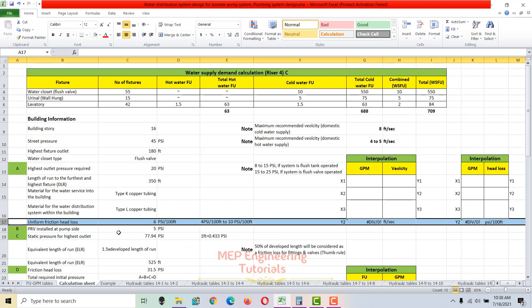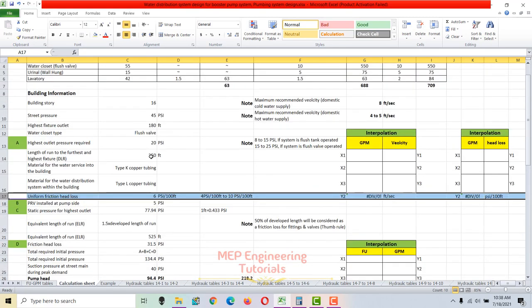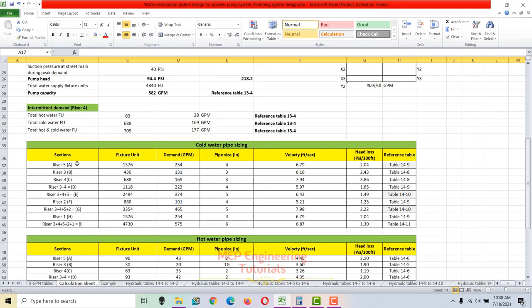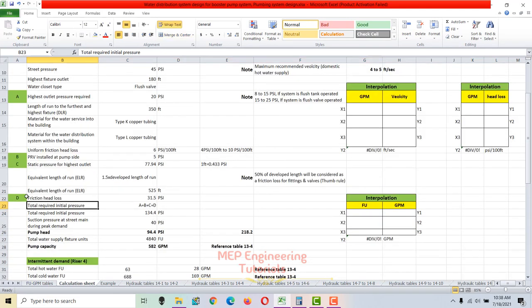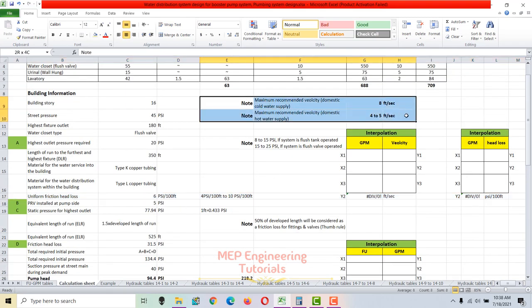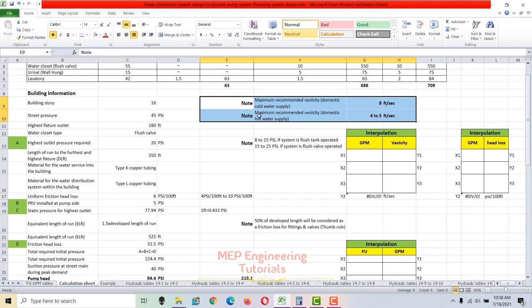We are going to use uniform friction head loss to calculate the hot and cold water pipe sizing. Two key constraints apply: the uniform friction head loss, and velocity. The maximum recommended velocity for domestic cold water supply pipe sizing is 8 feet per second, and for hot water supply it is 4 to 5 feet per second — so we use 5 ft/s for hot and 8 ft/s for cold.